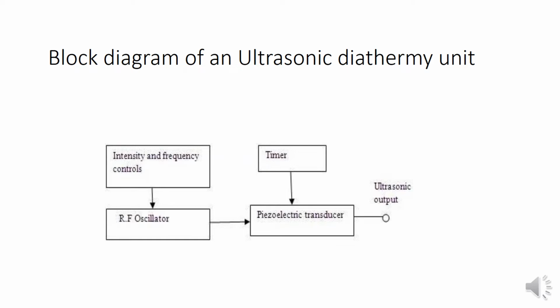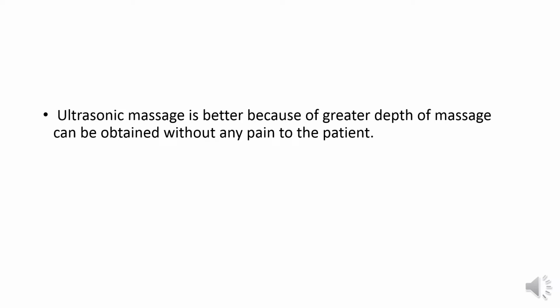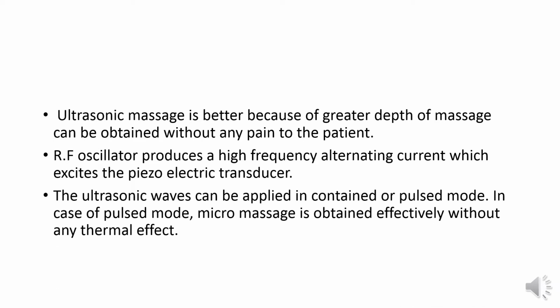Now we are going to see the function of ultrasonic diathermy. Ultrasonic massage is better because a greater depth of massage can be obtained without any pain to the patient. The RF oscillator produces a high frequency alternating current which excites the piezoelectric transducer. The ultrasonic waves can be applied in continuous or pulse mode. In pulse mode, the micro massage is obtained effectively without any thermal effect.